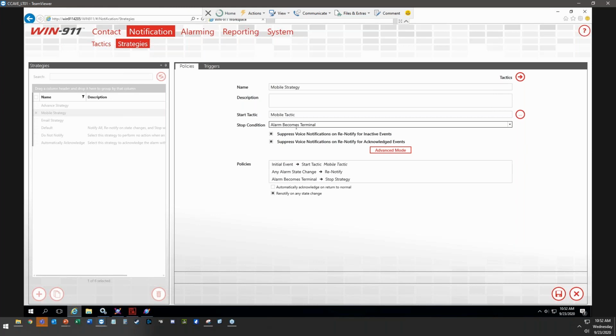However, let's say the alarm does come in as active, unacknowledged. An operator acknowledges that alarm, so it changes states to active, acknowledged. And at some point, if it were to go inactive, then at that point, it's completed its life cycle. It's become an inactive, acknowledged alarm. It completes itself. You would no longer see it in log viewer. And typically your SCADA alarm summary screen makes it disappear as well. And if that alarm were to trigger again within the next minute, 5 minutes or whatever, it becomes a new alarm with a new life cycle and it repeats the process.